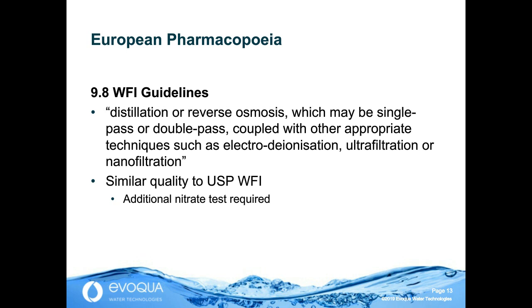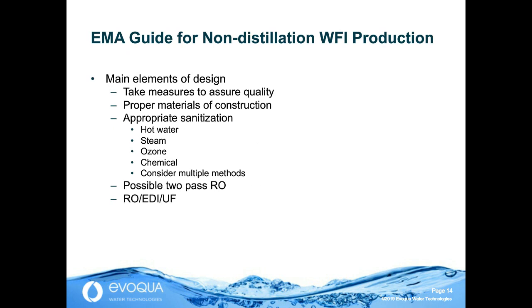Europe also has an EMA guide for non-distillation WFI, and the word consider is used throughout. So there are not necessarily explicit requirements, but appropriate materials should be considered. Sanitization is mentioned throughout, and more than one method is recommended. So hot water, steam, ozone, and chemical are proposed. Ozone is not compatible with generation equipment typically, just storage and distribution, but it means you could consider ozone and heat, ozone plus chemical, heat plus chemical.